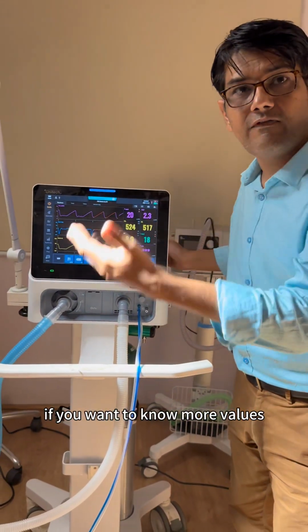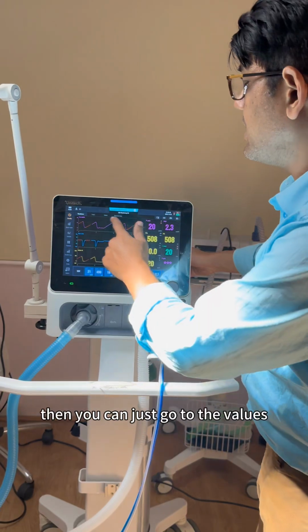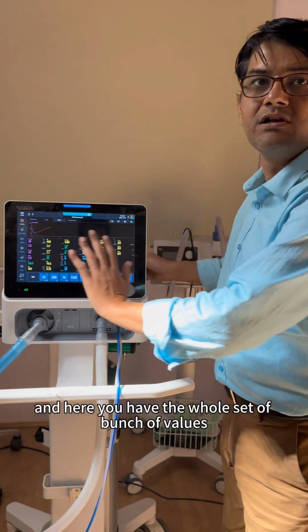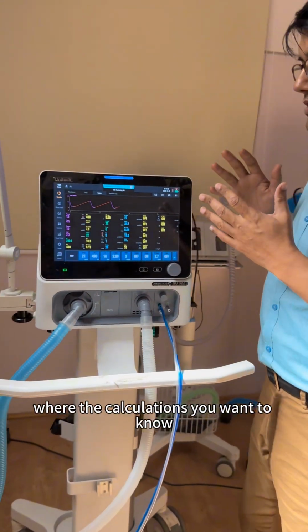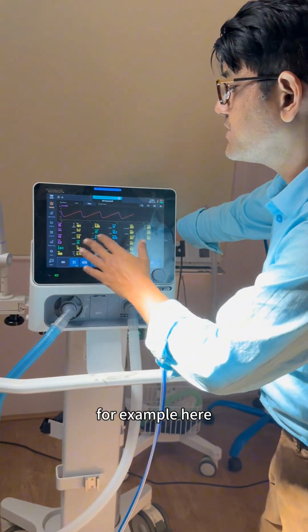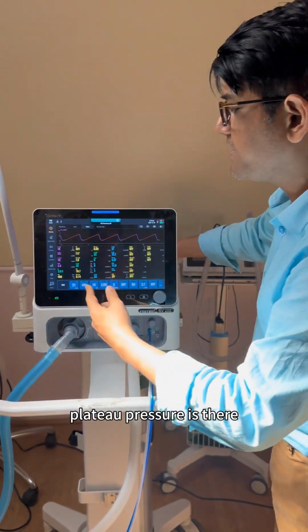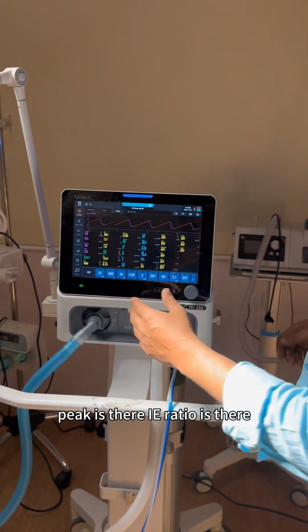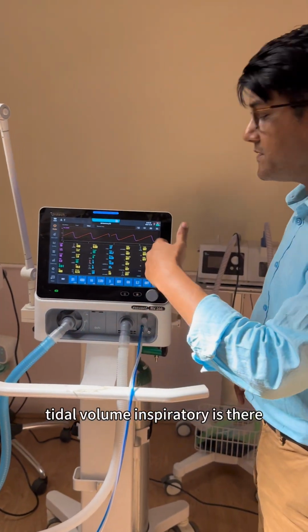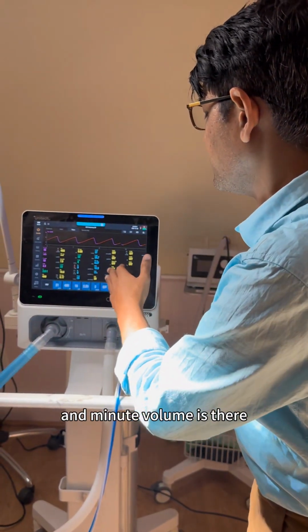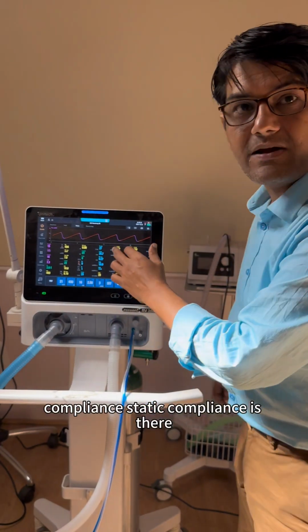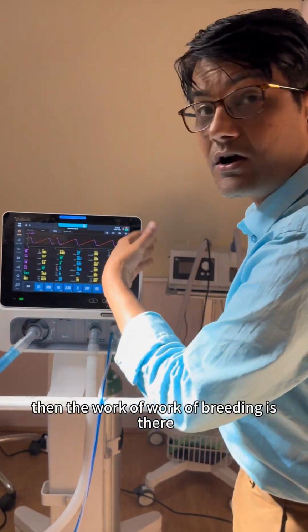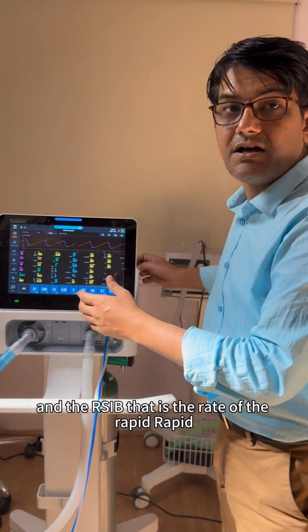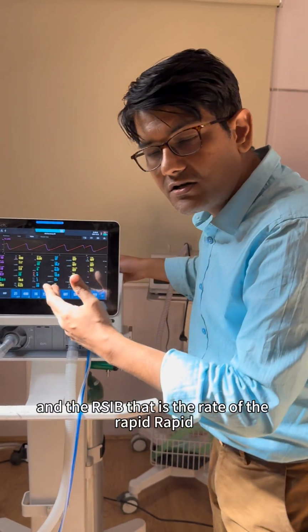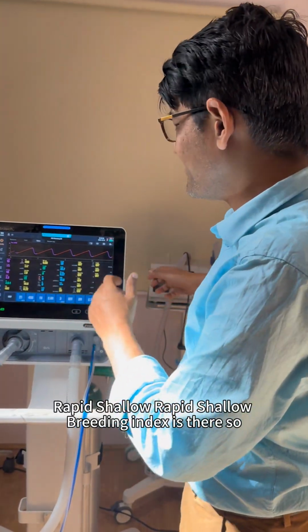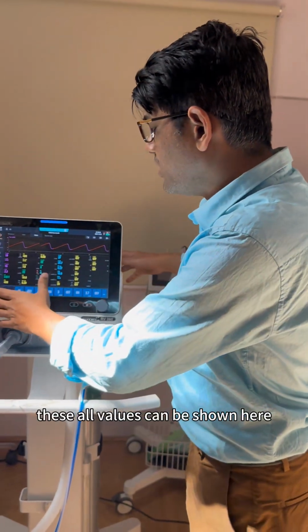If you want to know some more technical values, you can just go to the values, and here you have the whole bunch of values which you really want to know, the calculations you want to know, the patient's situation you want to monitor. For example, here you can see the peak pressure, plateau pressure, mean pressure, PEEP, IE ratio, the expiratory tidal volume, inspiratory tidal volume, and minute volume. Then you have the compliance, static compliance and dynamic compliance, then the work of breathing, and the RSBI, that is the rapid shallow breathing index. So all these values can be shown here.